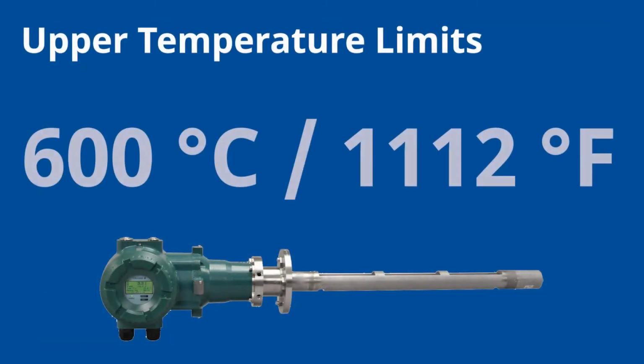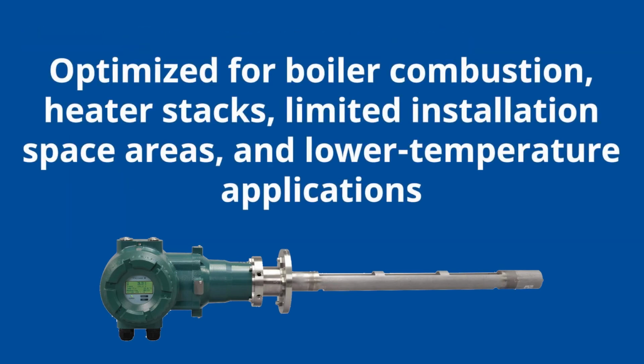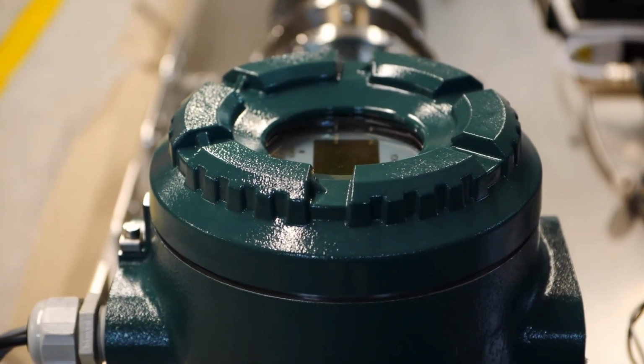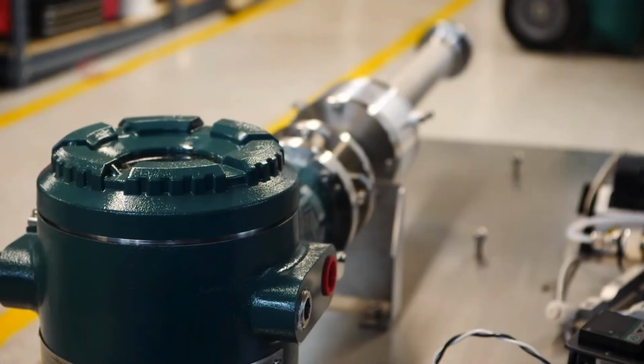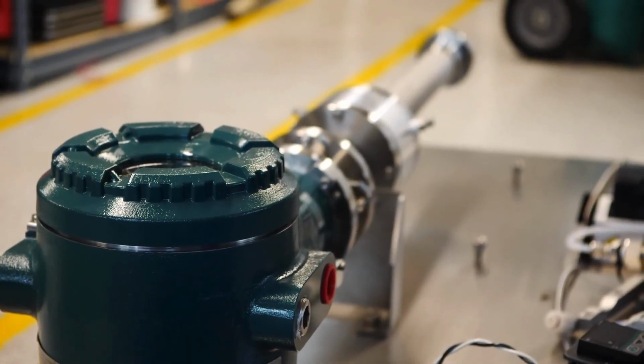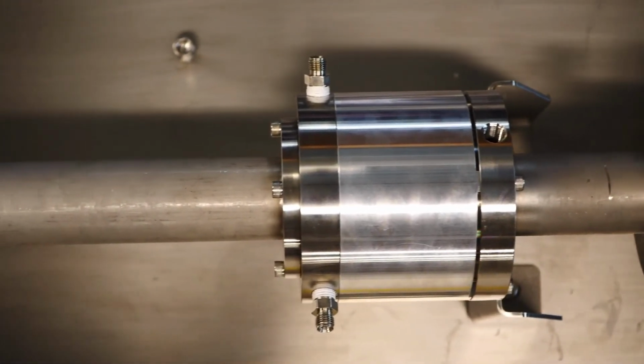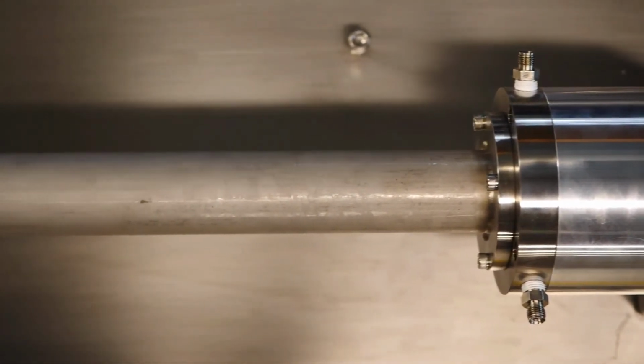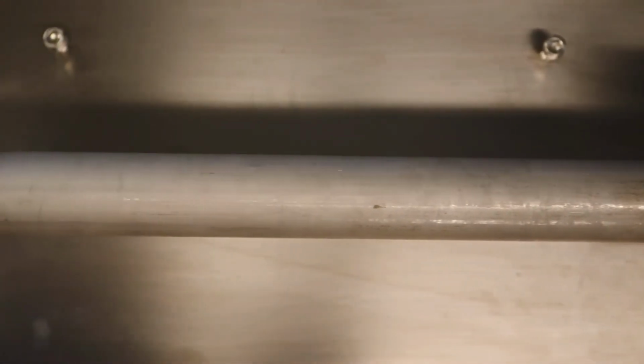Our upper temperature limit is currently 600 degrees Celsius or 1112 degrees Fahrenheit. The probe is optimized for boiler combustion, heater stacks, limited installation space areas, and lower temperature applications where current technologies have frequently poisoned consumables. We also have a sealed tube design of the TDLS8100 available for extractive applications. Samples up to 200 degrees Celsius can flow through the assembly at high flow rates and be kept within 1 degree C in the entire assembly due to our dual wall design. No zero offsets are required like for other technologies.